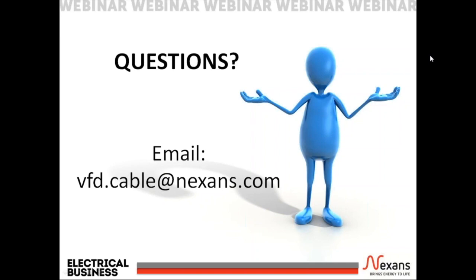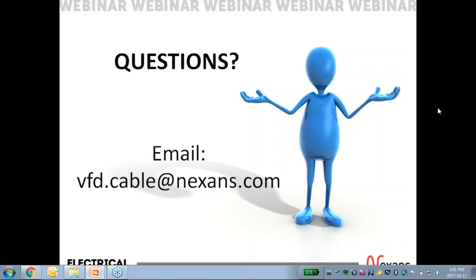Now, Kazi here says that you talked about connecting the cable shield to ground at both ends. Should cable deratings be considered when doing this, as the cable may heat up more during circulating current? Also a very good question. So it's been our experience that single conductor cables such as RA90 or our CoreFlex cable brand under Nexans, being aluminum sheathed over each individual conductor, if you bond both ends of that type of system where that aluminum sheath or that conductive material is around only one conductor, correction factors have to be accounted for the phase conductor ampacity. So in other words, a reduction in maximum phase conductor ampacity.